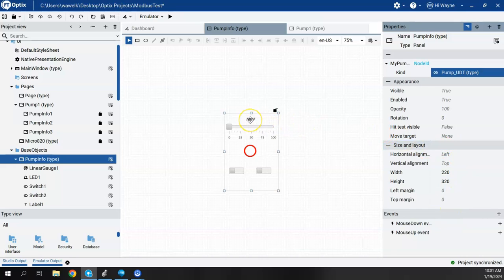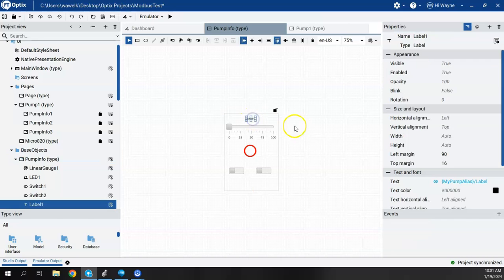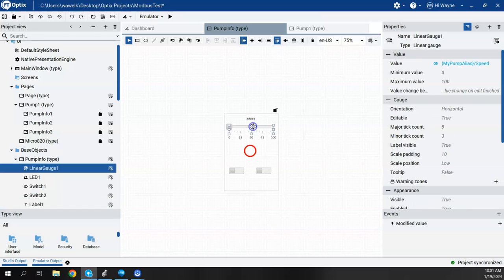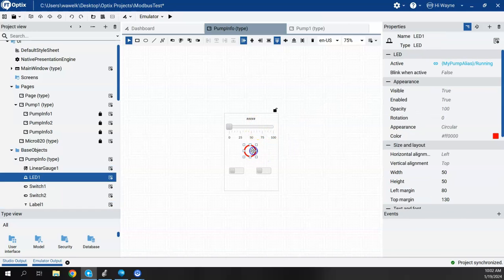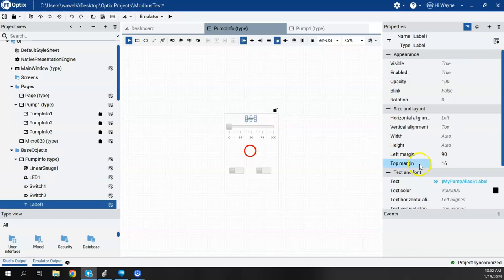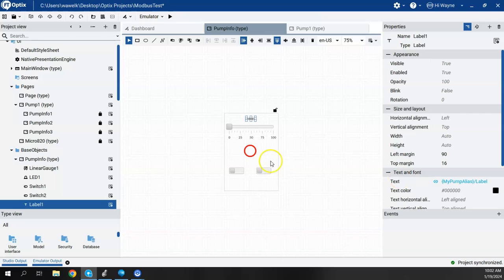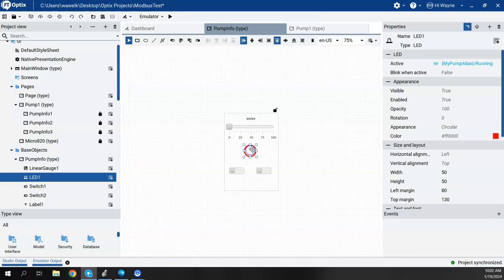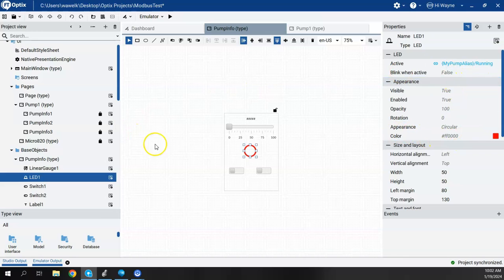And then since I kind of set this up nicely, I don't have to actually change any of the definitions down here for the three things that we were doing. We had a label, we had the speed, and we had the pump running indicator. And we weren't using these two on-off switches for this example. So for the label, it's still My Pump Alias and it's just tied to the label. For the speed, it's My Pump Alias and it's tied to the speed. And for the running, it's tied to My Pump Alias running. So when I created my UDT in the Logix controller, I kept all those names the same.